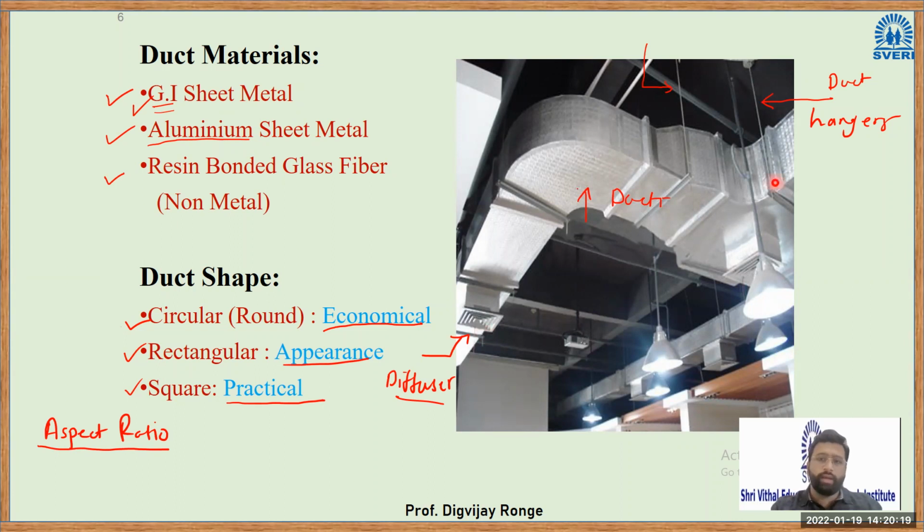What you see here is an internal part or layout of the duct. So these are the ducts. This was the main duct. Again, it has two branches, like this one and another this one. As branches take place, the flow rate decreases. With decreased flow rate, we decrease the size of the duct. So here the size of the duct is reduced. Then there is no sudden change in direction. असं डायरेक्ट काटा कोणात नाहीये. तिथे आपण काय दिलंय, राउंड शेप दिलेला आहे, because we want to reduce the pressure losses in the duct.